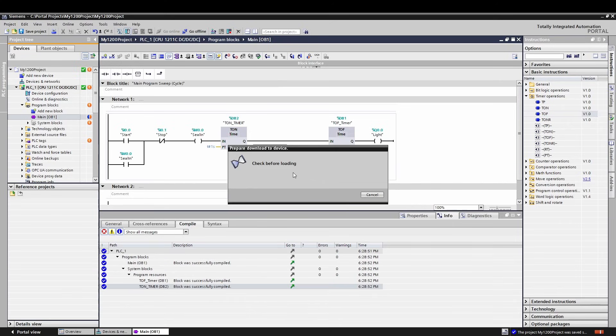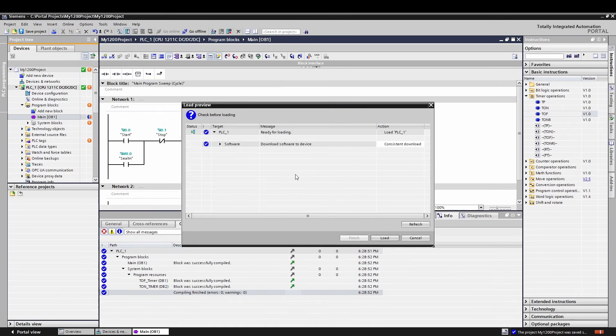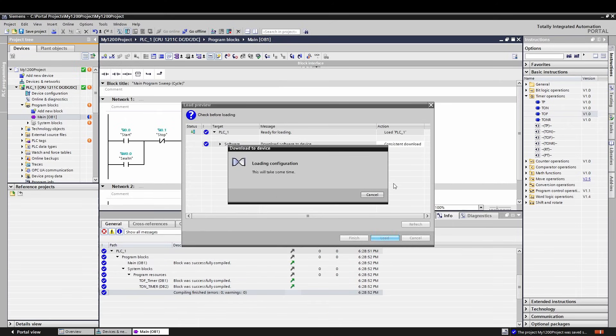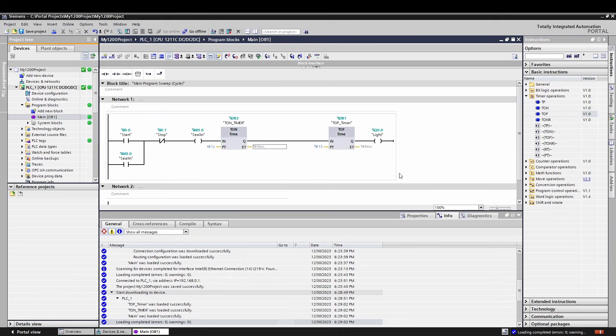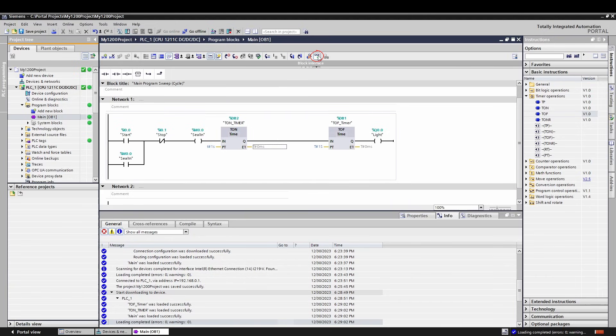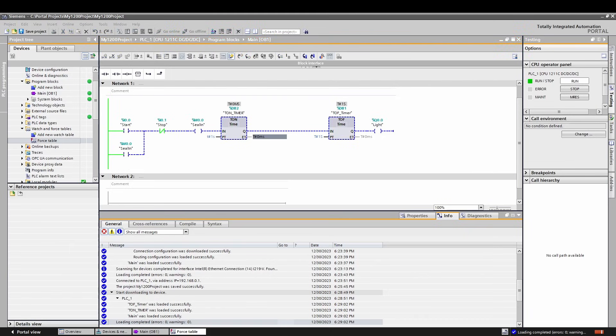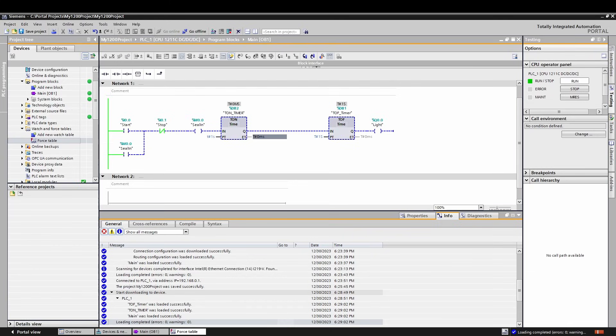Notice when you download it doesn't stop the processor. That means that you can load as much code as you want at the press of a button. If this sounds powerful, it very much is, but it also can get you into a lot of trouble if you aren't used to it. Remember, this PLC isn't running a video game, it's running a piece of equipment that could actually injure or kill someone. So let's see this in action by pressing the monitor button. It has the little glasses. We press start, the output comes on after one second, and after another second... nothing. Crap. The first timer needs to be reset once it times out in order for the TOFF to start.